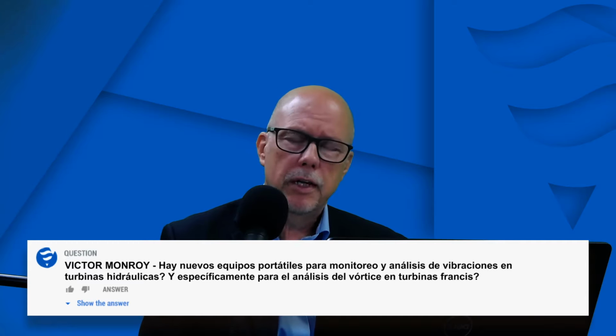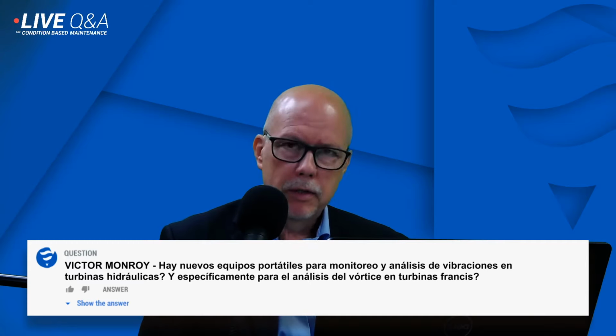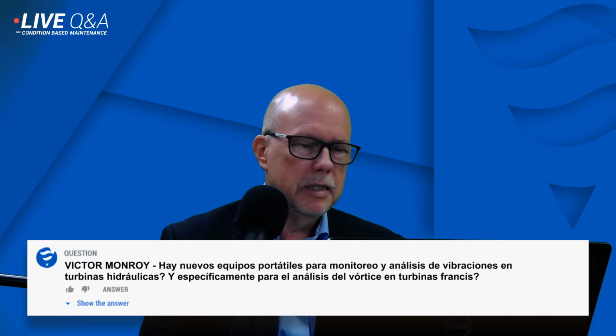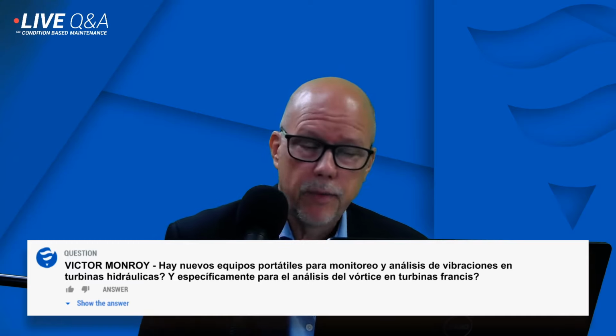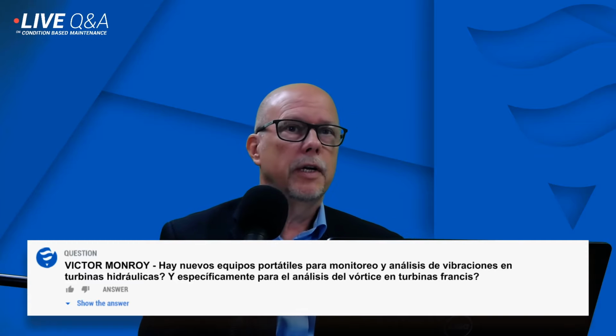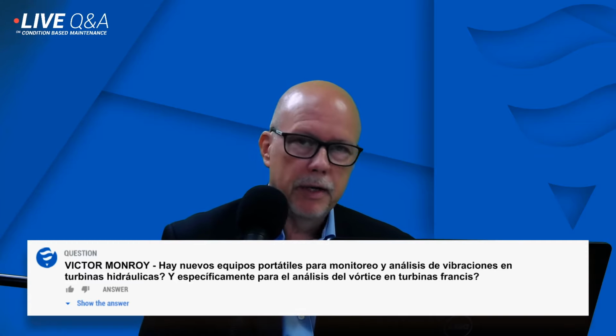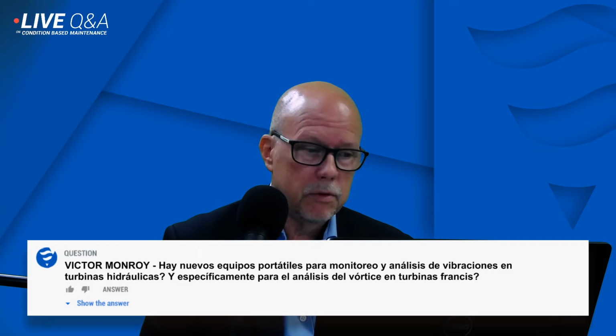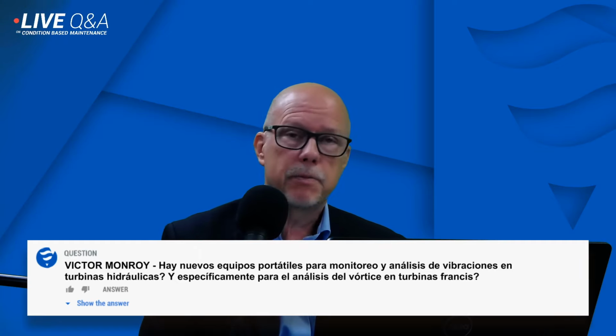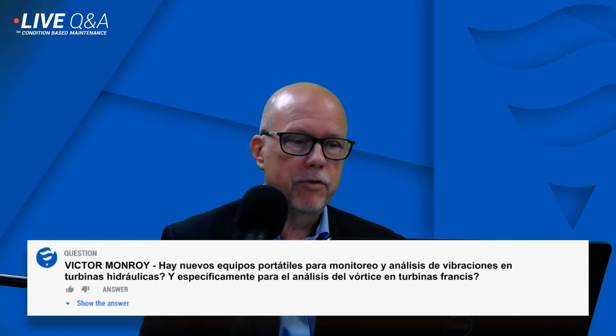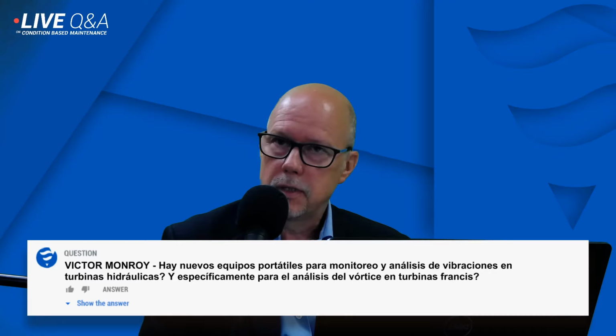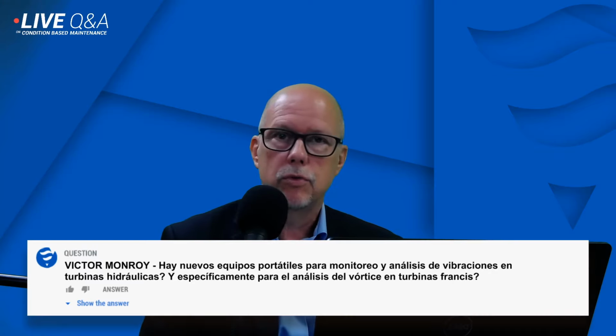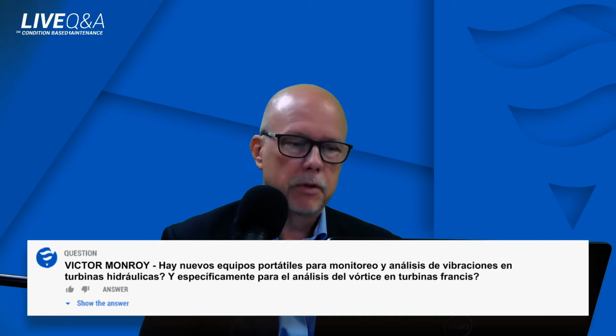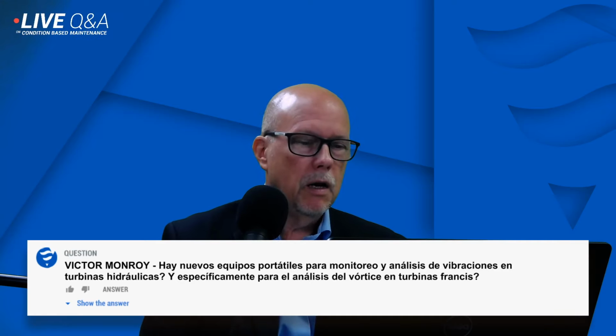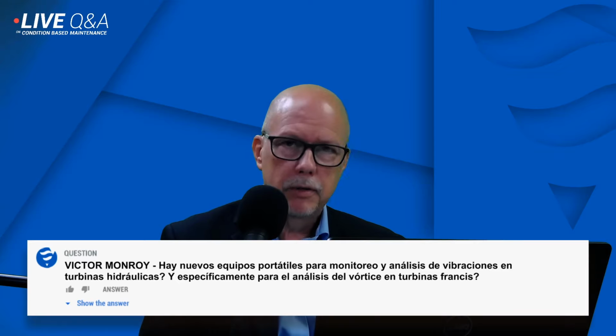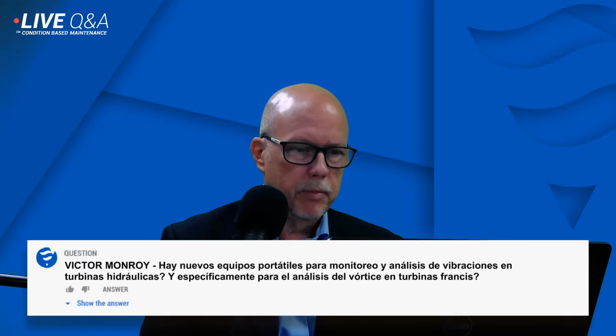We believe that to do that, you need to have online permanent monitoring so that you can see, for example, hydro generators in the northern hemisphere. They quite often have very different behaviors depending whether it's summer or whether it's winter. Just the concrete of the dams will expand and contract, and it will change the behavior. And if you have a portable system and you take readings once a year in June, well, you'll never see that type of behavior. So we believe in online permanent installation, so we don't really sell portable equipment.